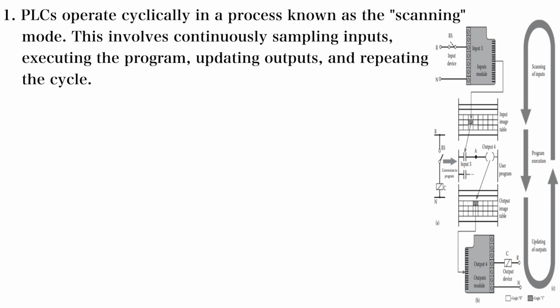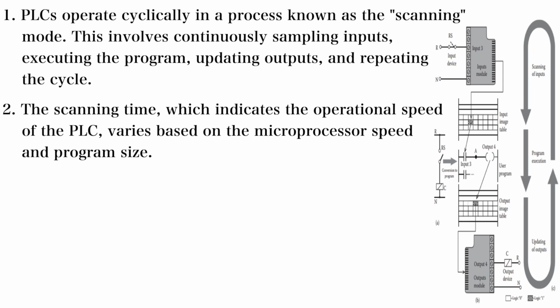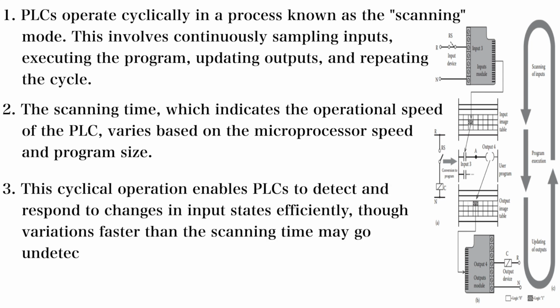Programmable logic controllers mainly operate cyclically in a process known as the scanning mode. This scanning mode involves continuously sampling inputs, executing the program, updating the outputs and repeating the same cycle. This scanning mode has a scanning time which indicates the operational speed of the PLC operation, and it can vary based on the microprocessor speed and also on the program size. This cycle operation enables PLCs to detect and respond to changes in the input states efficiently, though variations that occur faster than the scanning time can go undetected. So for proper operation, the variation should not be faster than the prescribed scanning time. If it is faster than the scanning time, then it will go undetected.